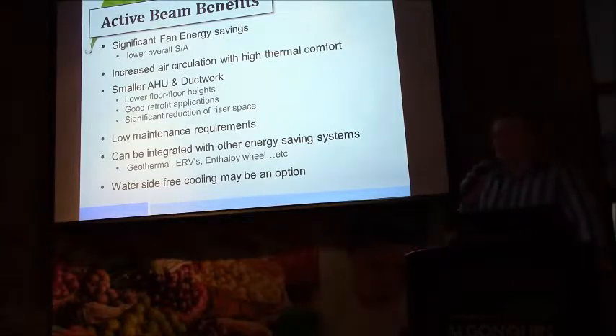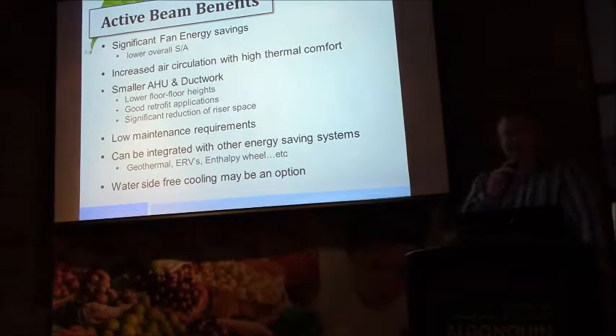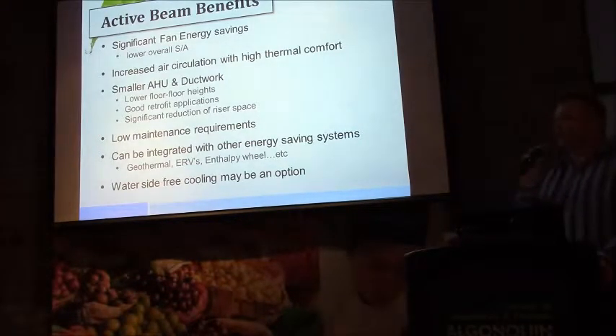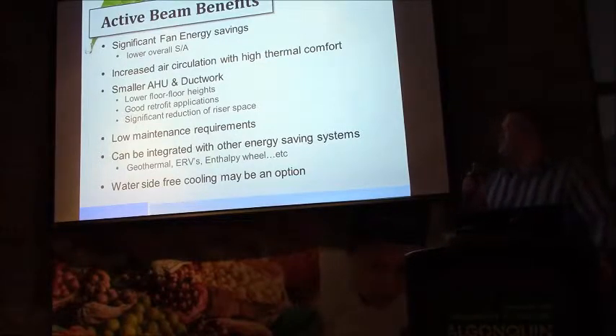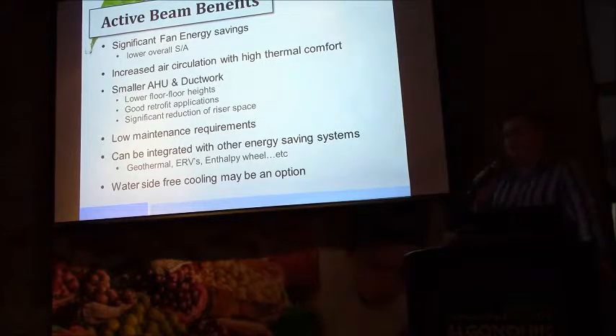It improves the cycle time between filter changeouts, and incrementally it's maybe a box size on a compartmental unit or some prepackaged piece of equipment. It's not a huge premium to pay for that peace of mind and ultimately that opportunity to be able to repurpose the space, given that nearly every building will see that. Great for retrofit applications, again, very tight spaces. Beams oftentimes are installed in ceilings that can be less than 12 inches in terms of bottom of the ceiling to under slab of the floor above.